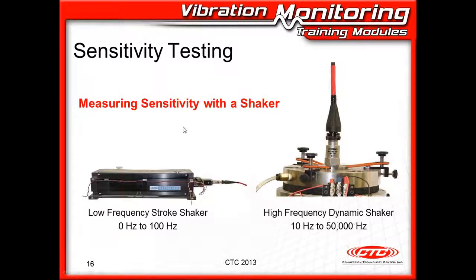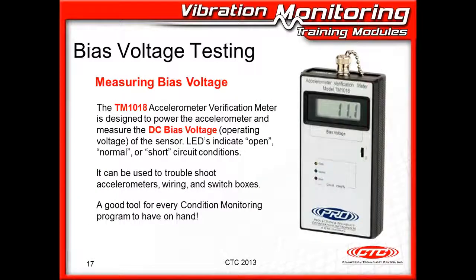So to test the sensitivity or to calibrate the accelerometer, you really need 2 different shakers. Now, it's a good rule of thumb out at the site or at the mill to have at least a single point shaker. And typically, especially in the metric system, that's going to be running at 159.2 hertz. And what that'll do is give you 10 meters per second squared at 159.2 hertz and allow you to see that one sensitivity. So that's kind of nice to have because it's a quick check type of device that you can use right at your site.